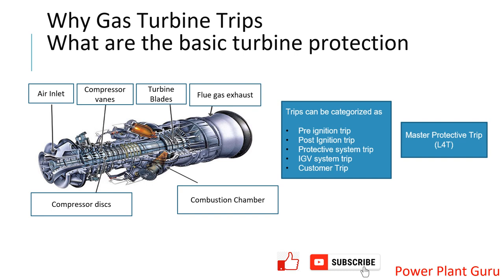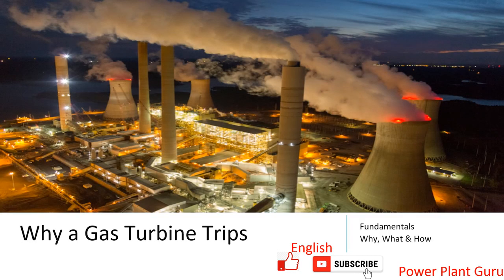Hello friends, welcome to Power Plant Guru YouTube channel. In today's video we will see why a gas turbine trips, or for instance why any turbine trips. What are the basic protections provided in turbines to prevent catastrophic failure. A gas turbine may trip on various conditions like over temperature, over speed, vibration high, control system failure, turbine compartment fire, gas leak, etc. There are so many things, but all those can be categorized and understood one by one.